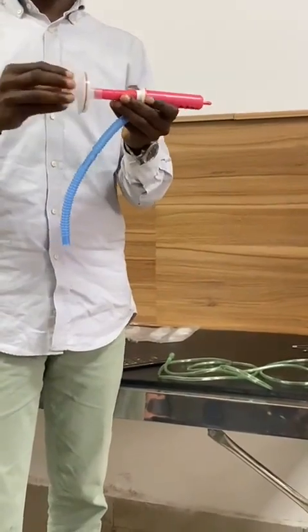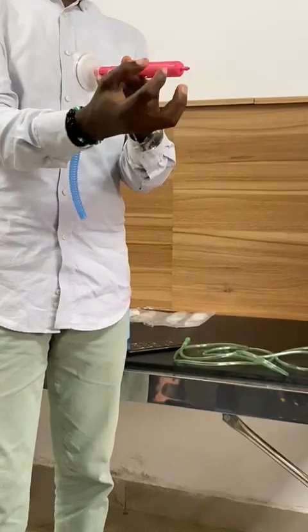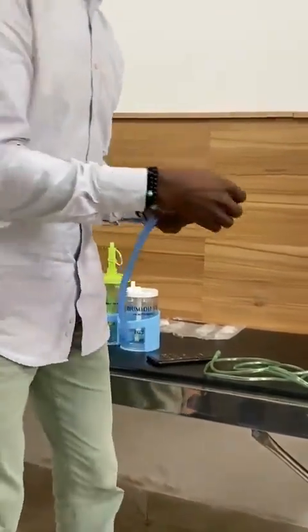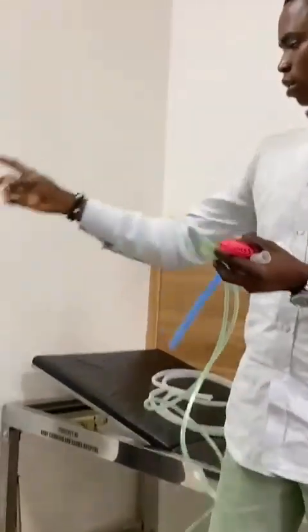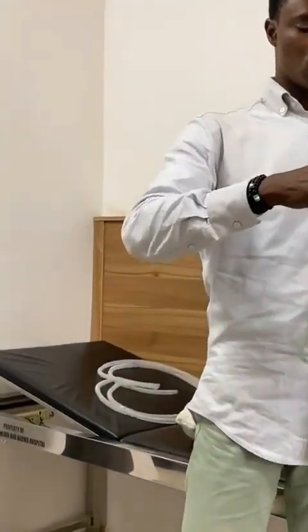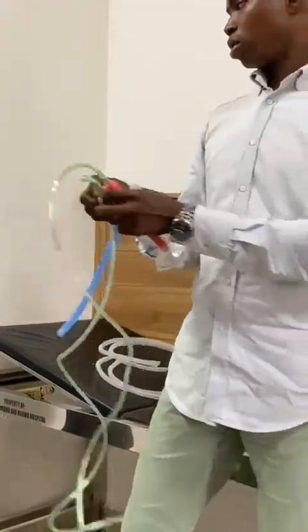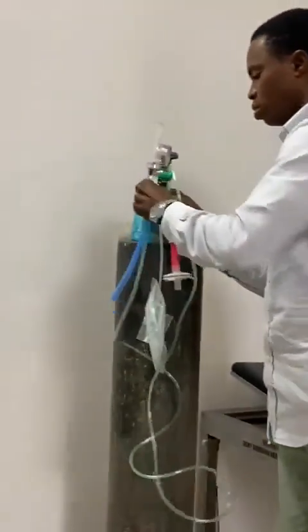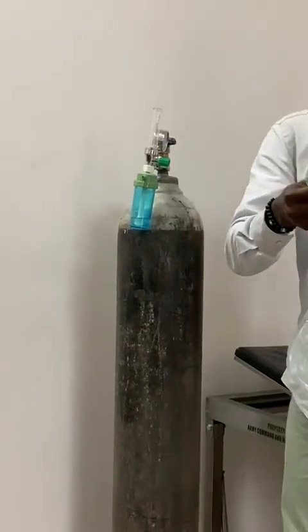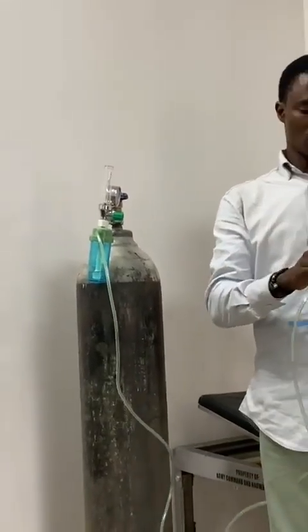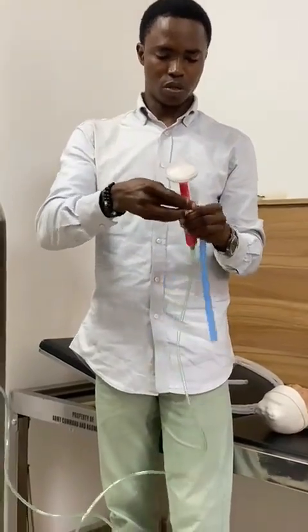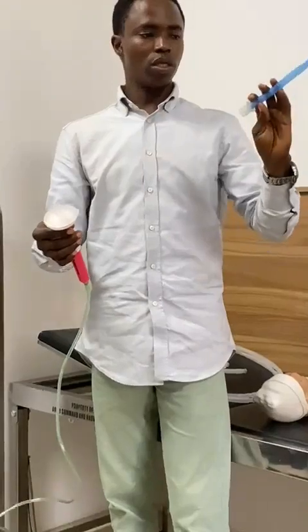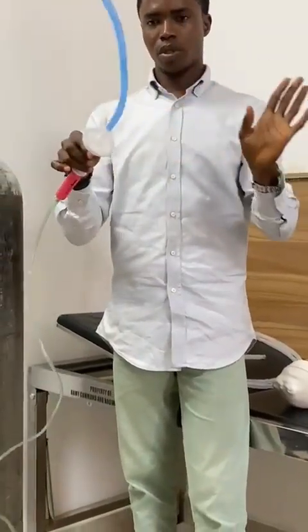So from this Venturi system it goes to your filter, because the gas mixture comes through here. Now, how do you connect your oxygen? You have this tube here, and it also comes with the machine. Just put one end here, then the other end goes to your oxygen source. You understand to this level, so then you lock. As soon as you lock, it doesn't move again. Then you see this blue connects to your filter.